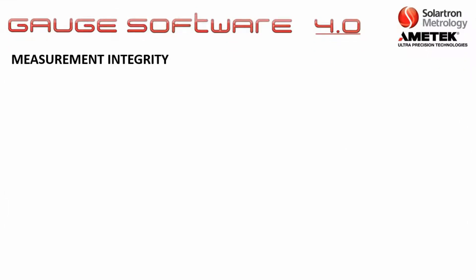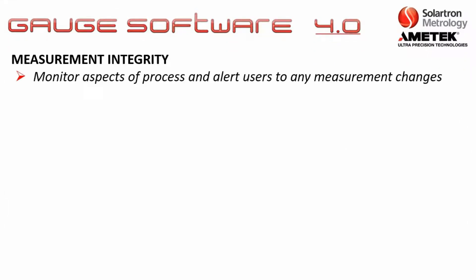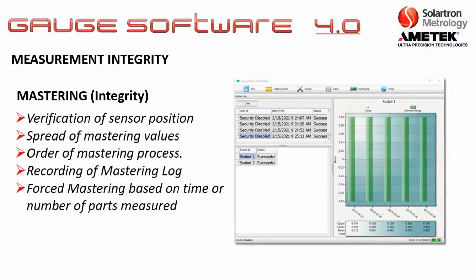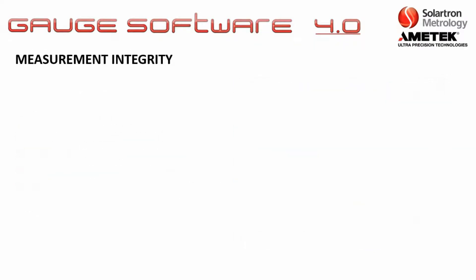There are also multiple features for measurement integrity, which is basically the monitoring of aspects of the measurement process and will alert users of any measurement changes. One example is mastering integrity, which includes verification of sensor position, the spread of mastering values, the order of the mastering process, recording of the mastering log, and forced mastering based on time or the number of parts measured.